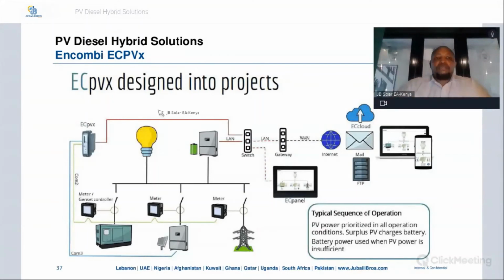And this is how the ECPVX is designed into projects. Here we have three different energy sources. We have the grid with its meter, we have the PV array with its meter, as well as the genset with its meter or controller. All these are connected to the ECPVX. From here, you are able to monitor on the EC panel, or remotely on your computer or on your phone. Another source I'd forgotten to mention is the battery solution. So with these four sources, they can all be controlled by the ECPVX, and all this information is relayed through the EC Cloud to your monitoring platform. This could be remotely or on the EC panel that is on the EC Cube.